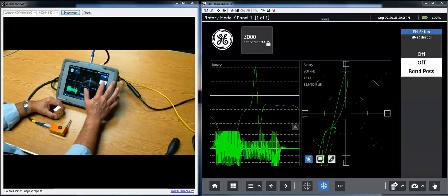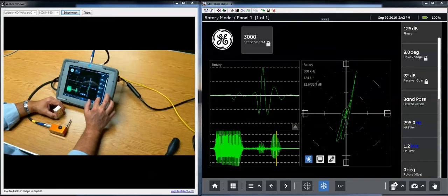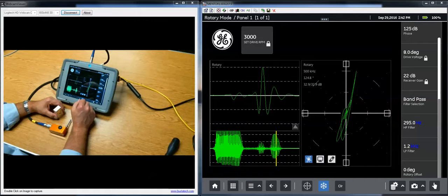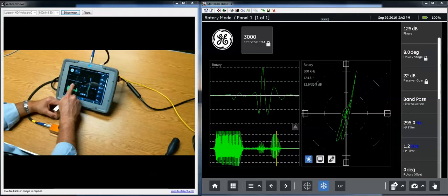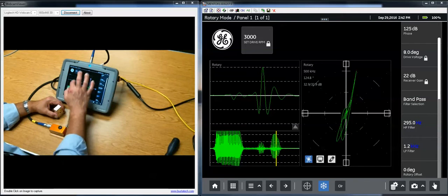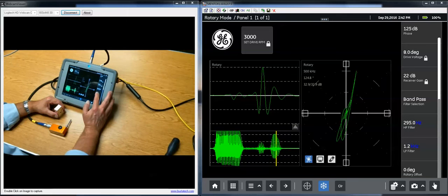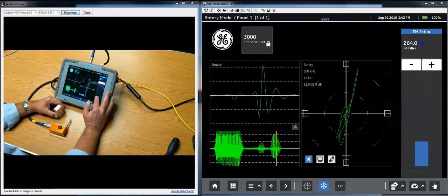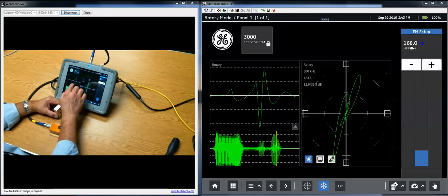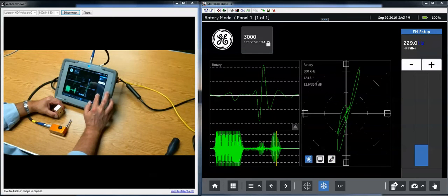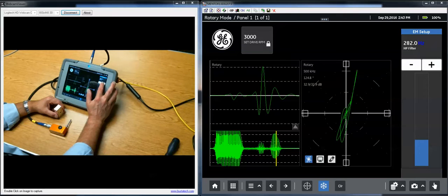When the filters are set properly, the high pass and low pass cutoffs for the filter, you'll get an indication that looks very much like this from a notch. You'll get two little descending sacks underneath and one ascending indication from the notch itself. If you look at the filter response on a time-based view, these bottom two legs of this response you want to be of roughly equal height, and the indication in the center tells you something about the size of the notch. So we can come in here and we can change our filtering, and you notice as we adjust the cutoff frequencies of the filters, everything recalculates, redraws, and we begin to lose the shape that we were looking for. So if we come back in here and we make subtle adjustments to our filters, we can get those two legs roughly equal.